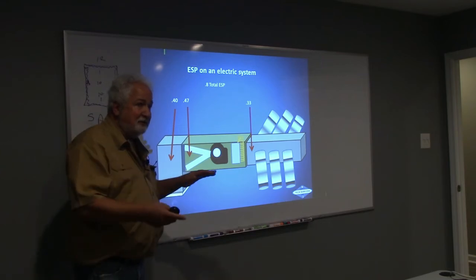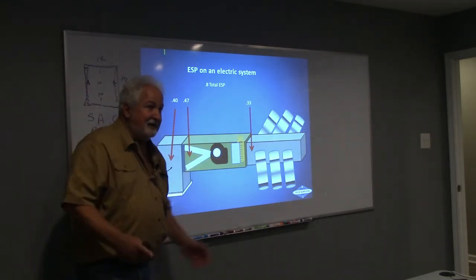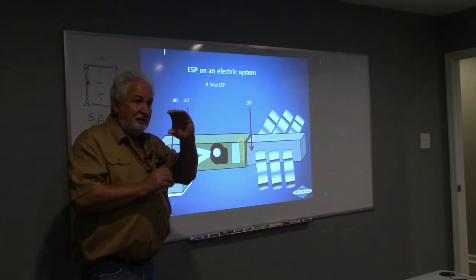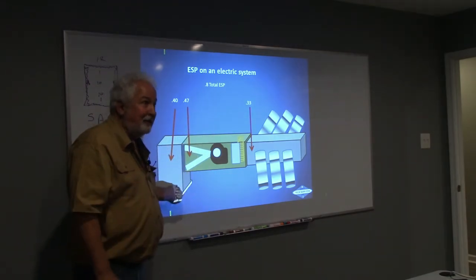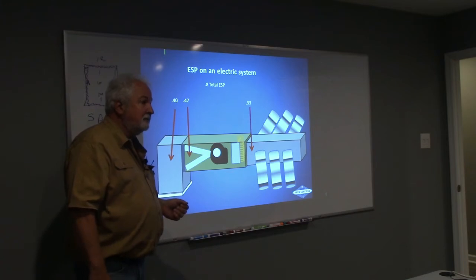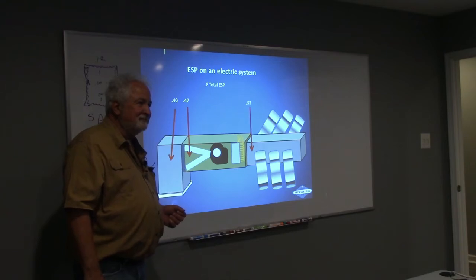I've seen Jody send me some pictures the other day. We got this much space down here and it goes up and it turns and it has to go through a little hole this big. So the little hole is where the problem's at, right? Yes, sir. You know what we see quite often, which I know you've seen 100 times, you probably see them on service calls, where they think that just because they cut a hole this big in the wall, that it can still go through this stud cavity. That's only a 2x6. And then it gets to a can in the attic that stands up this tall, but it's still only this big. And they think that that's...